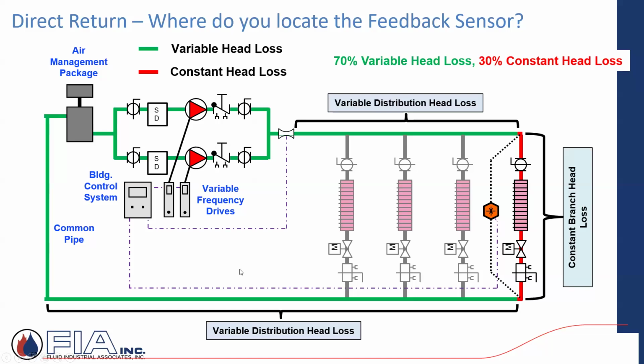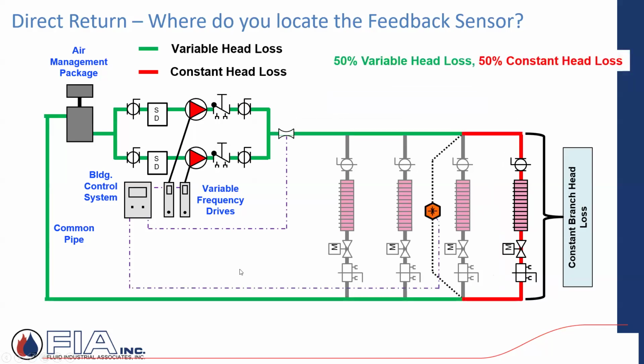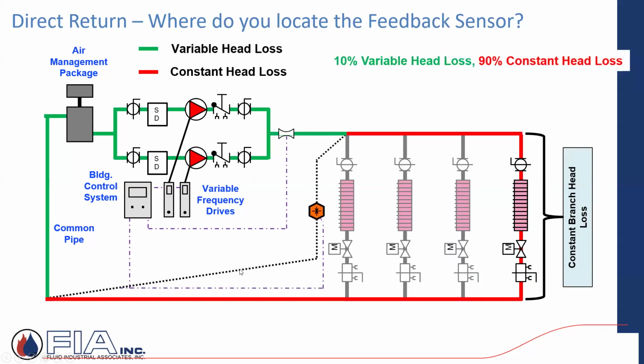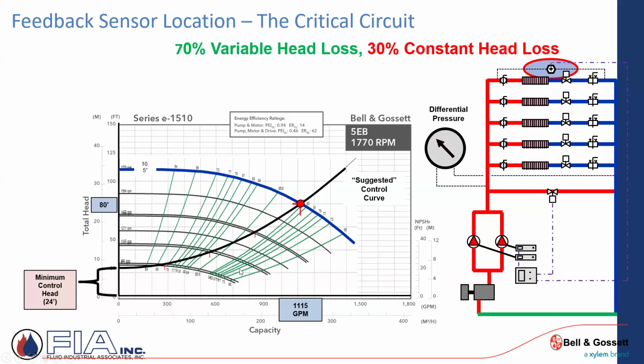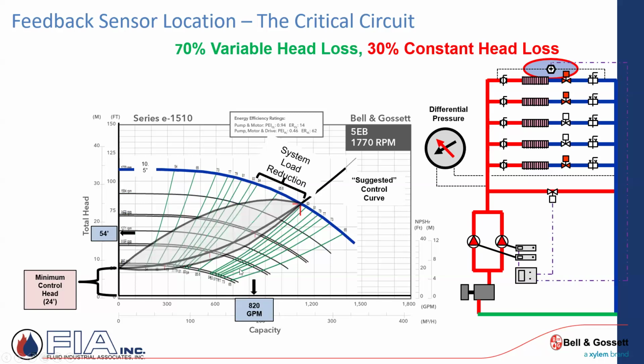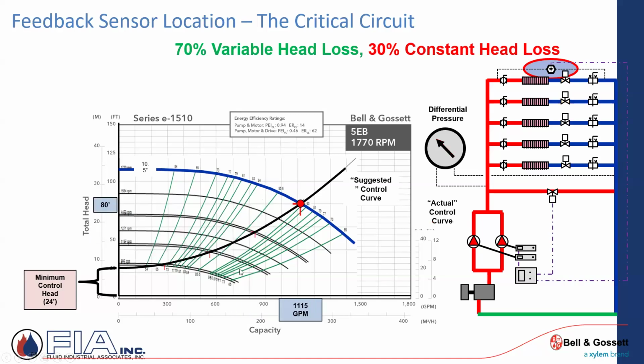And again, variable 70% versus 30%. Going back, kind of repeating myself there. This is just giving us a quick example here. Here's that 70% variable with a 30% constant. I'm all the way out in the system. As those valves close, I can back up the pump curve, which normally is what I would do if I was fixed speed. But because I'm variable speed, I'm just changing that speed. I'm reducing the speed. And in doing so, I've reduced that flow and then the required pressure drop, the 54 feet of head versus the original 80 feet of head. I still have that minimum control head out at that remote terminal unit.